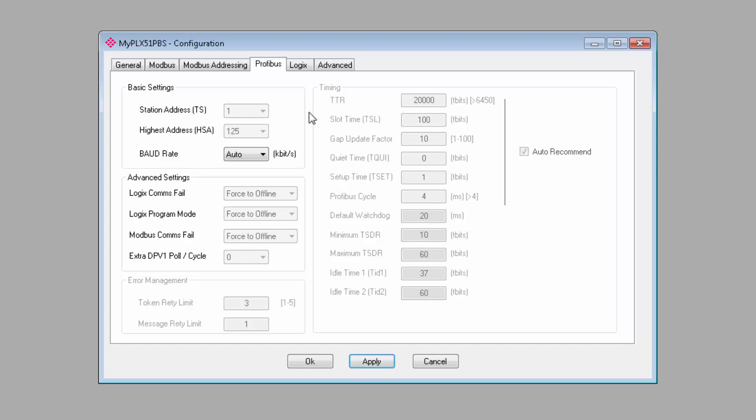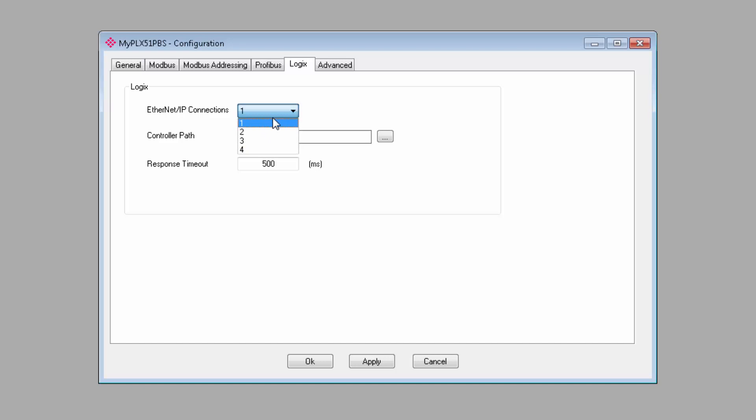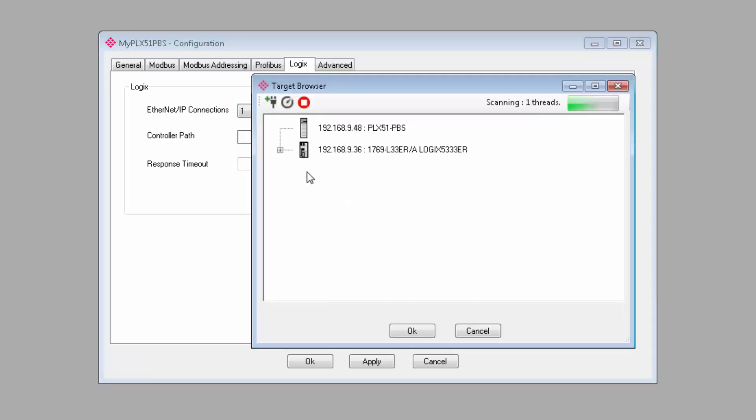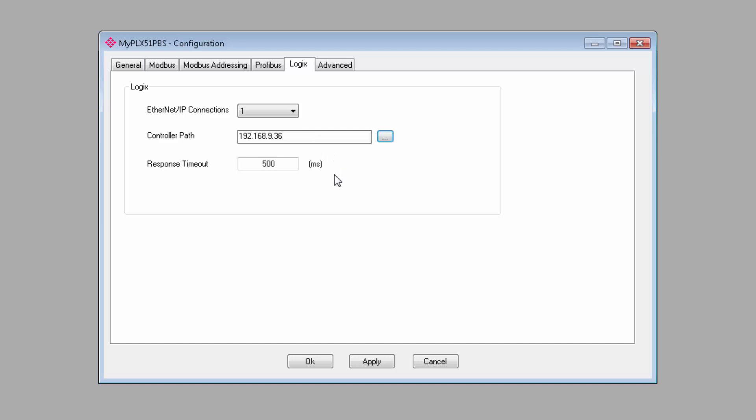Moving on to the Logix tab, we can configure the connection to a Logix processor and whatever I.O. or other devices may lie beyond. The Ethernet IP connections count will depend on how much I.O. you'll be connecting to. One EIP connection should be good for 500 bytes of input data and 496 bytes of output data. If you need to transfer more data than that, you can add up to four connections. I'm going to leave it at 1 for this training, and I'll click the Browse button to locate my CompactLogix controller. Once I have it, I'll click OK, and it will appear in the Controller Path field.